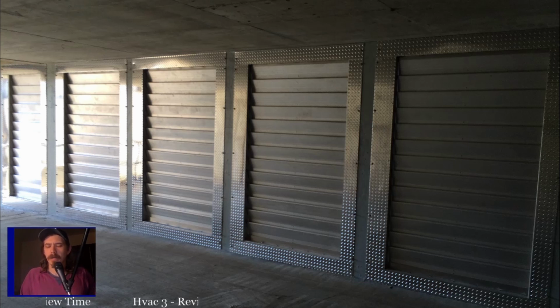And generally speaking, switches are going to fail in the positions that they're naturally at. So if the switch is closed almost all the time because it never opens up, then a lot of times it's going to fail in that closed position. The only difference being bimetal switches like motor overloads and things like that, because that metal tends to fail as it expands to break the circuit. Those tend to fail in that open position if they're overheating a lot, because the metal doesn't go back to the position it was very well after a lot of cycles on it. So just something to keep in mind.